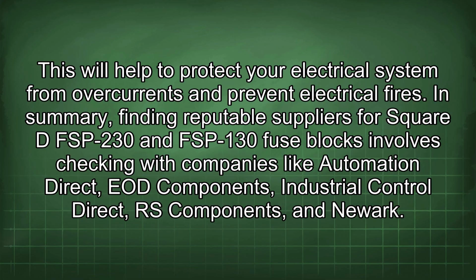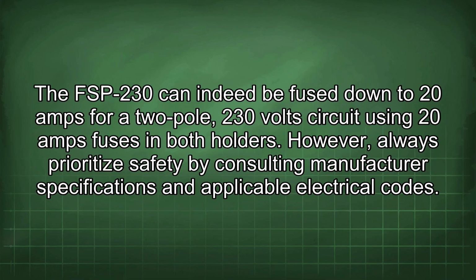In summary, finding reputable suppliers for Square D FSP-230 and FSP-130 fuse blocks involves checking with companies like Automation Direct, EOD Components, Industrial Control Direct, RS Components, and Newark. The FSP-230 can indeed be fused down to 20 amps for a 2-pole, 230-volt circuit using 20 amp fuses in both holders. However, always prioritize safety by consulting manufacturer specifications and applicable electrical codes.